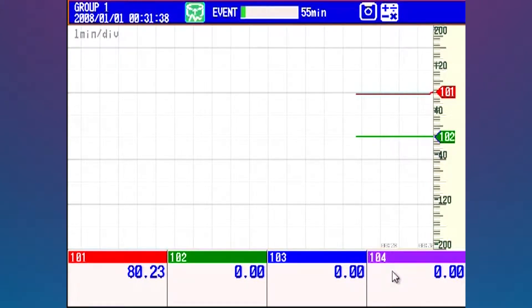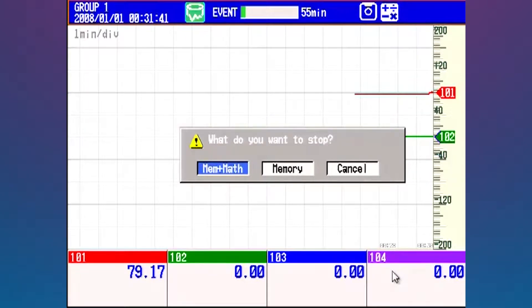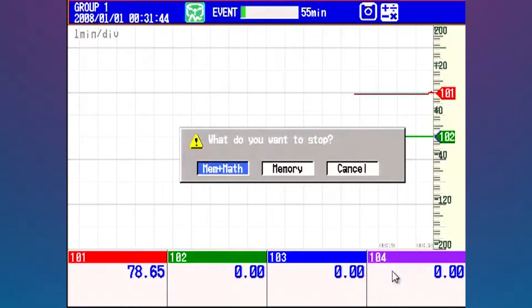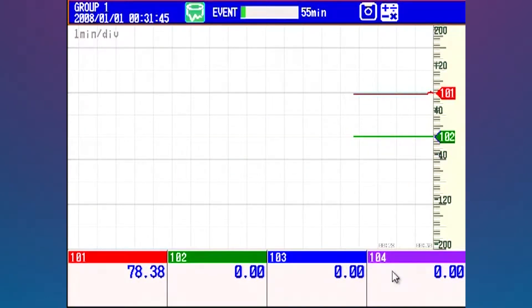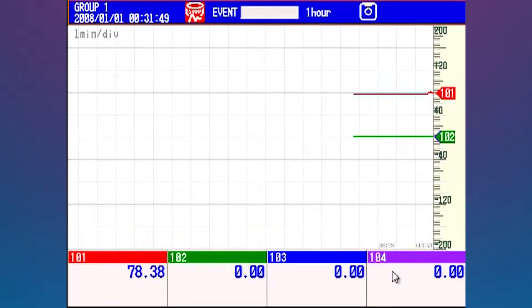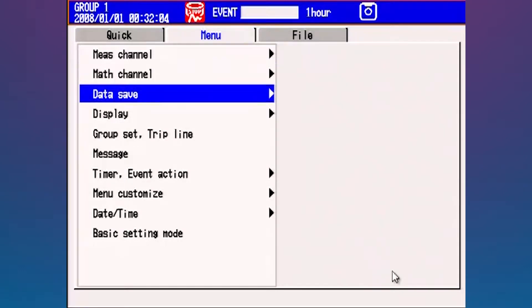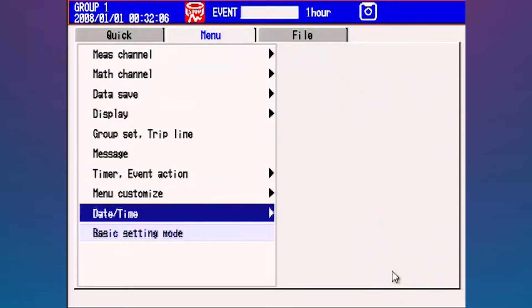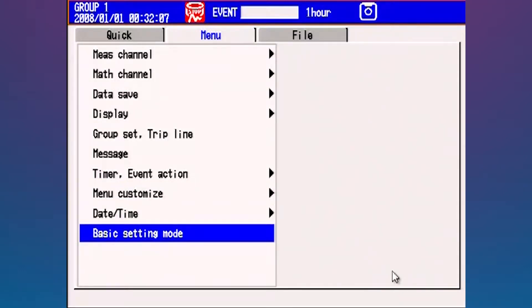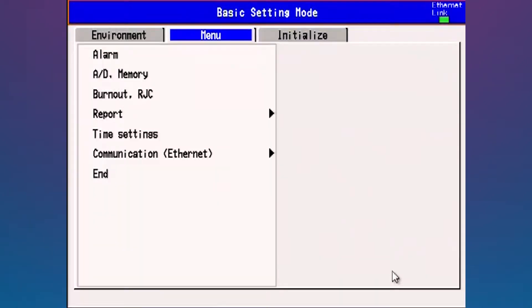I'll grab the thermocouple quickly and we should see a rise in that 76.1, which is my office temperature here. And we can see that it's doing a pretty good job of bringing in that remote temperature input from the MW100. I'm going to hit the start stop button to stop memory and math, then hit the display enter key to stop the unit, then press the menu key to go to the first level menu. Let's go down to basic setting mode at the bottom.